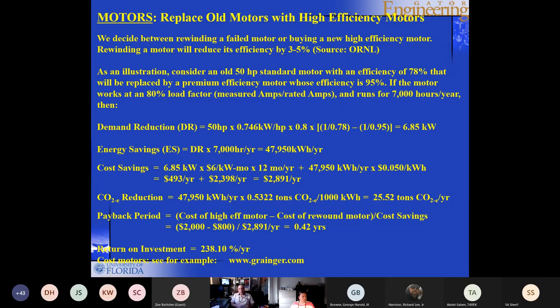Now, if you rewind the motor, the downside is that your efficiency will get reduced by 3 to 5%. Every time you rewind a failed motor, you're going to lose 3 to 5% of the motor efficiency. That's the Oak Ridge National Lab, which is the source for those of you that would like to dig this up.